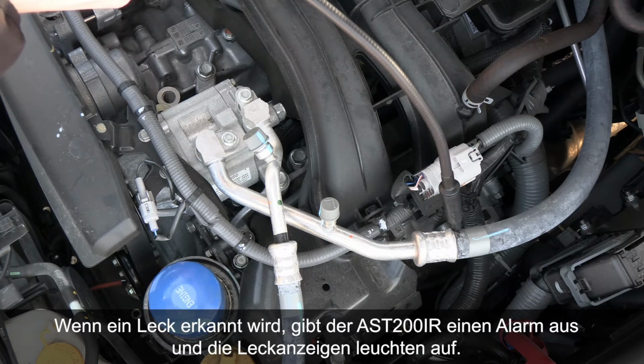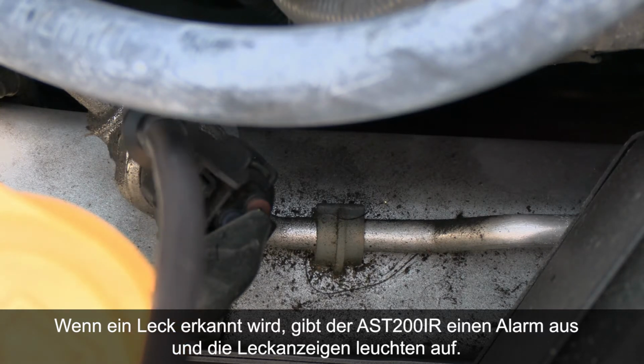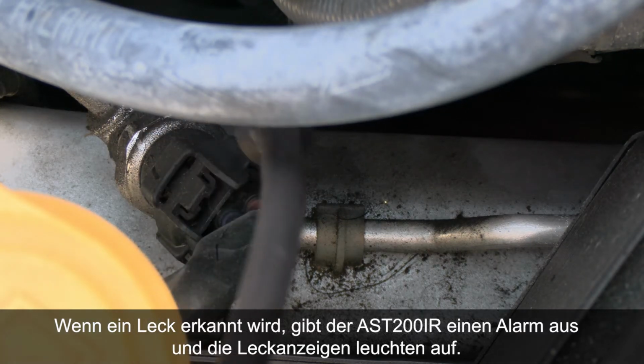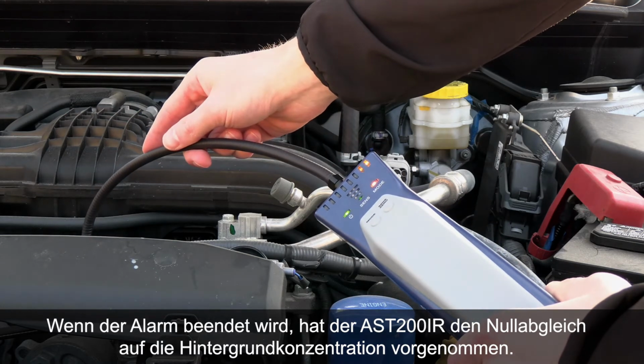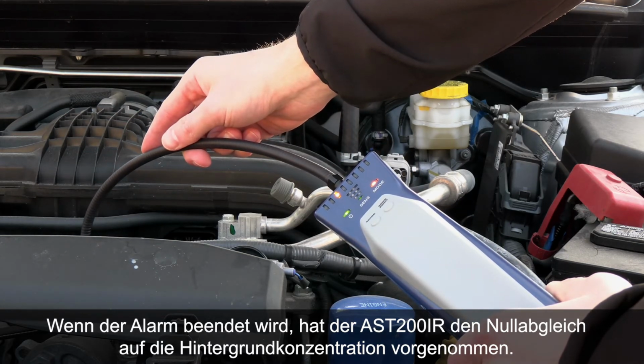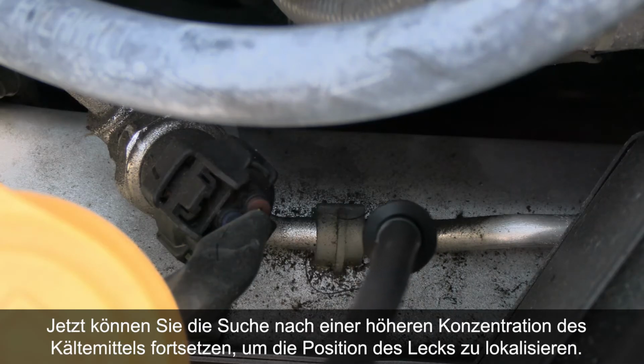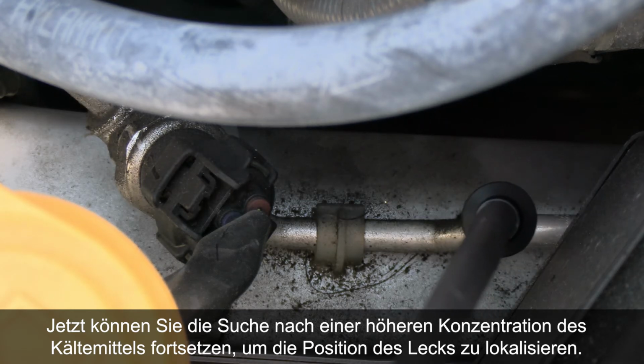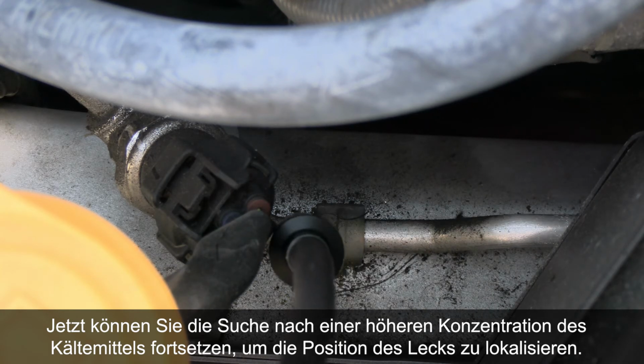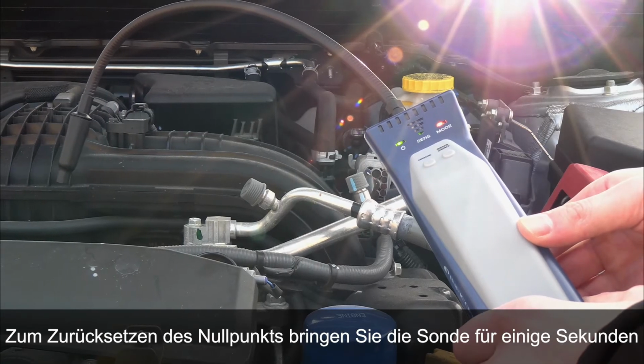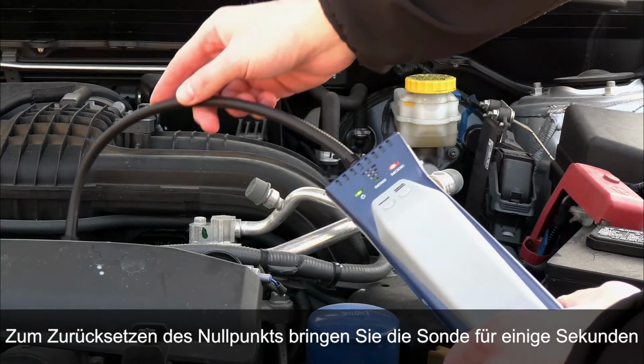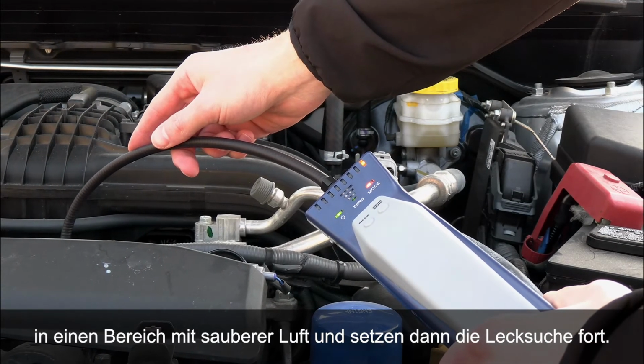If a leak is detected, AST200IR alarms and the leak indicators illuminate. When the alarm stops, AST200IR has zeroed to the background. Now, you can continue looking for a higher concentration of refrigerant to pinpoint the leak location. To reset the zero point, move the probe to clean air for a few seconds, and then check again to verify the leak.